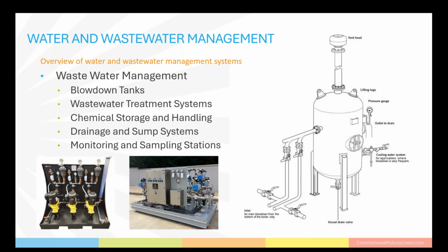Layout considerations for wastewater management. We want to position the blowdown tank near the boiler with consideration for gravity flow and drainage. Wastewater treatment systems should be located near the blowdown tank or water intake with easy access for maintenance. We want to place chemical storage and handling in the designated area with secondary containment and spill prevention measures. We want to design drainage and sump systems to collect and manage wastewater with easy access for maintenance and inspection. We want to locate monitoring and sampling stations throughout the plant.